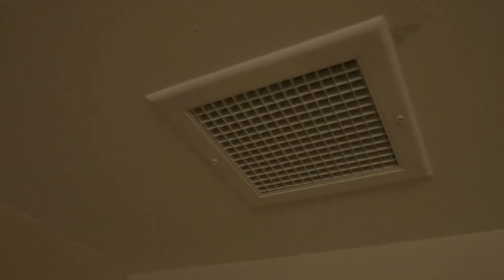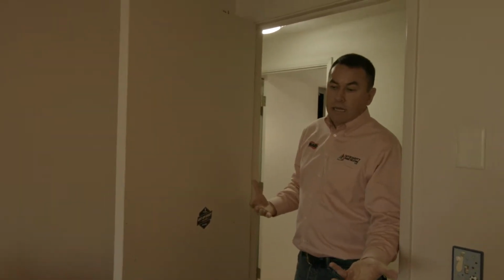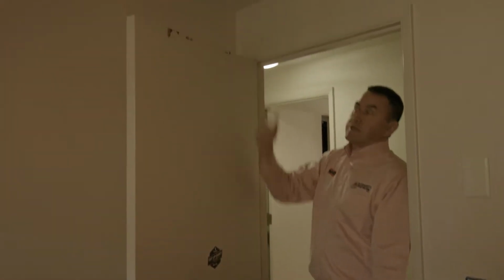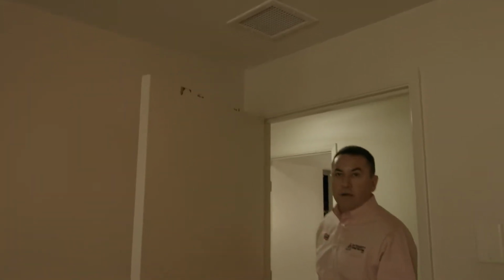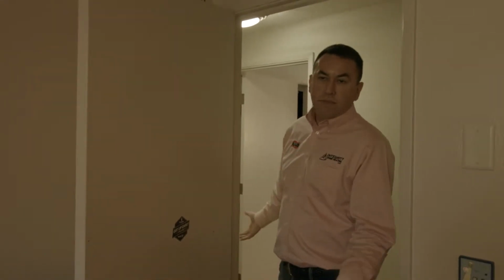supply vents. And also, in addition to the main return, we put a smaller return in each bedroom. What a smaller return does is, if the bedroom door is closed, it still draws air out of the room back through the filter, cleans the air. So if your system is on and you're supplying the air, you're pressurizing the room, you have a return vent that's drawing air out. So the more return air out of different sections of the home, the better.